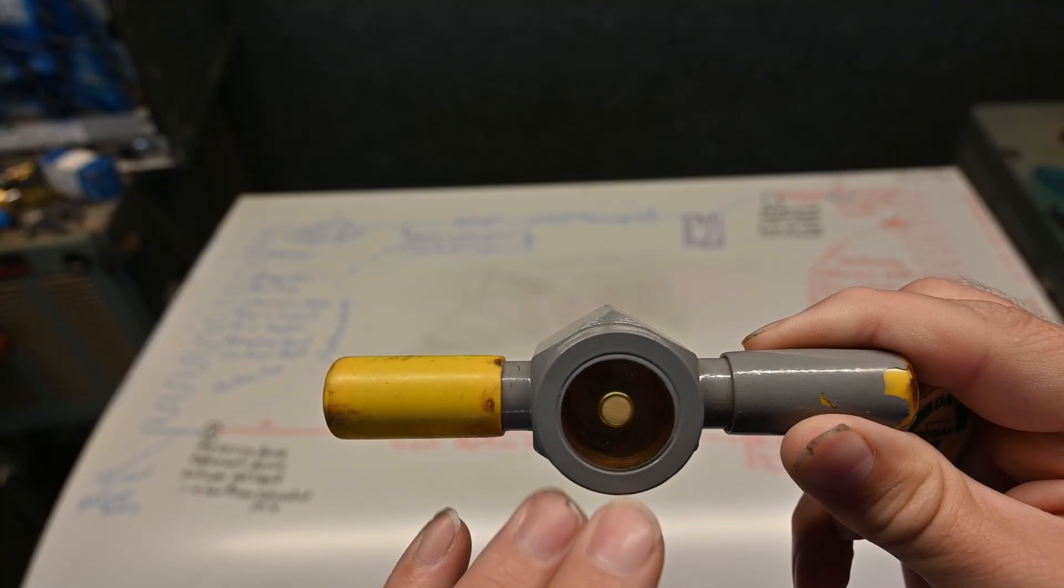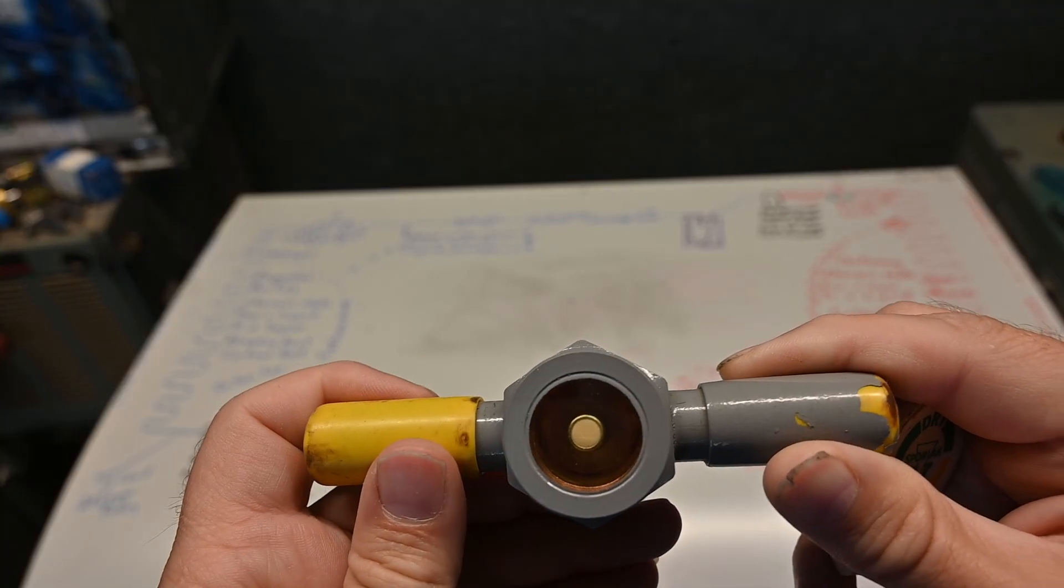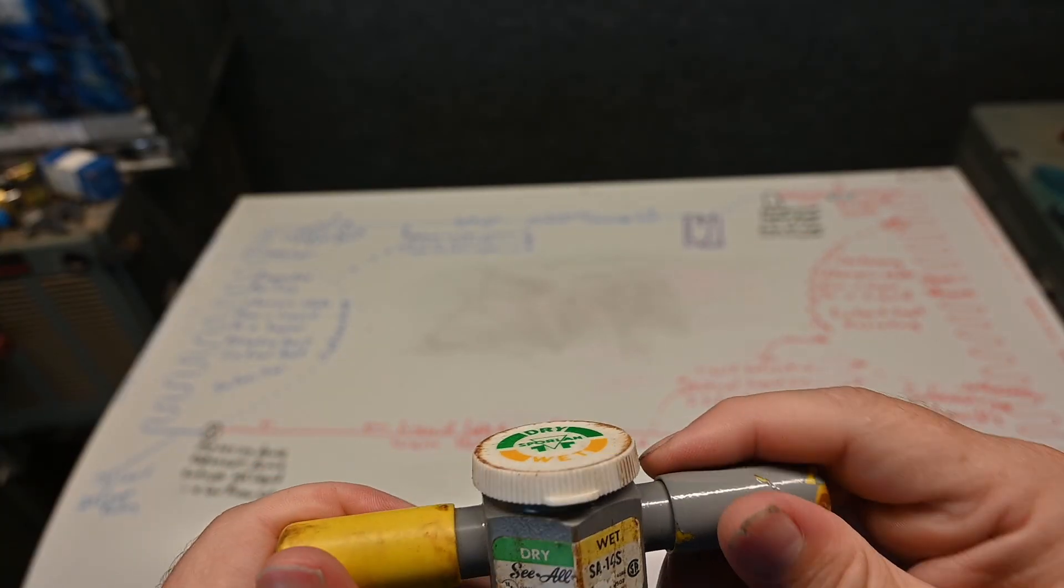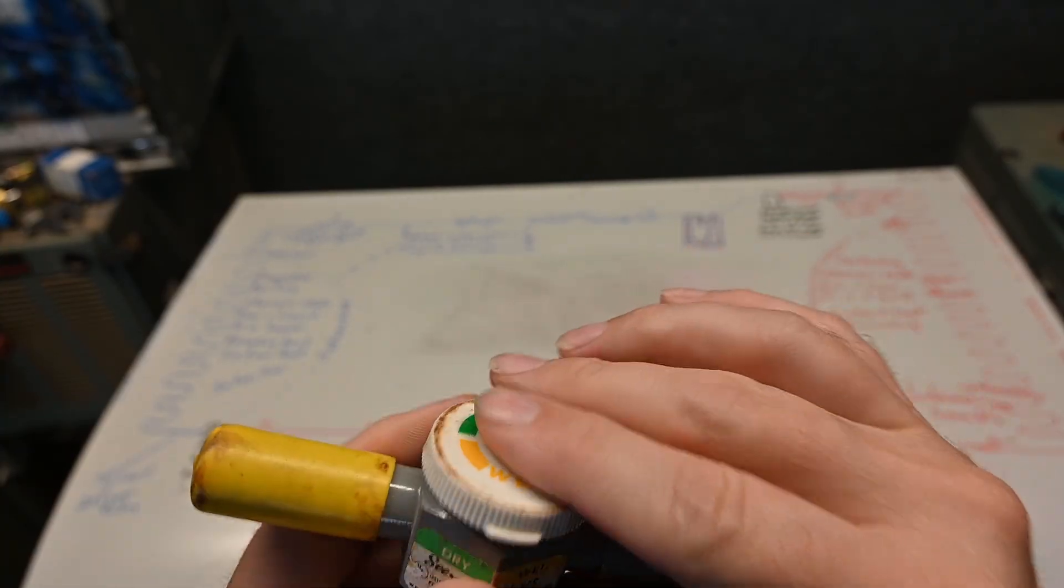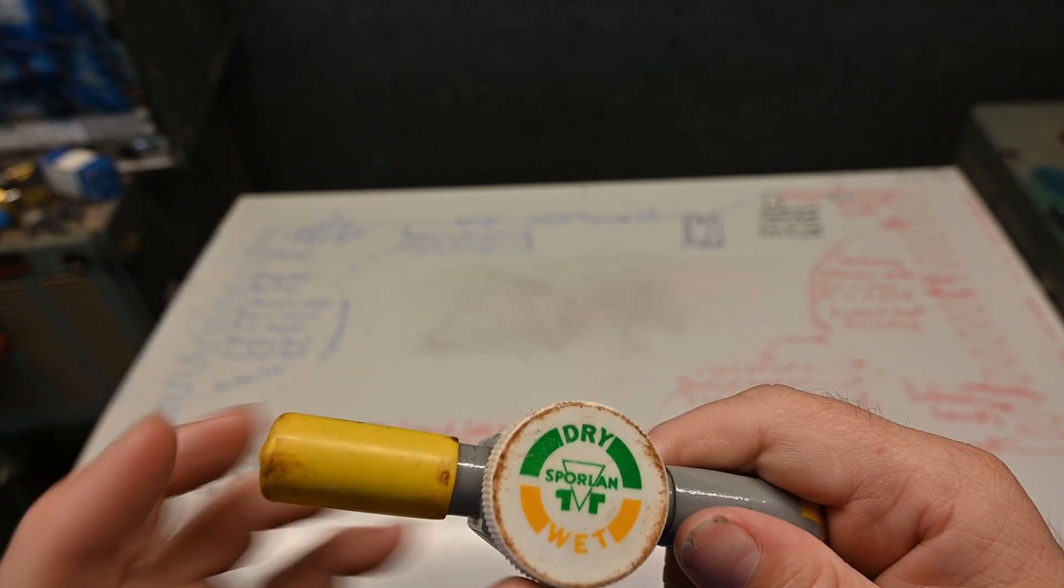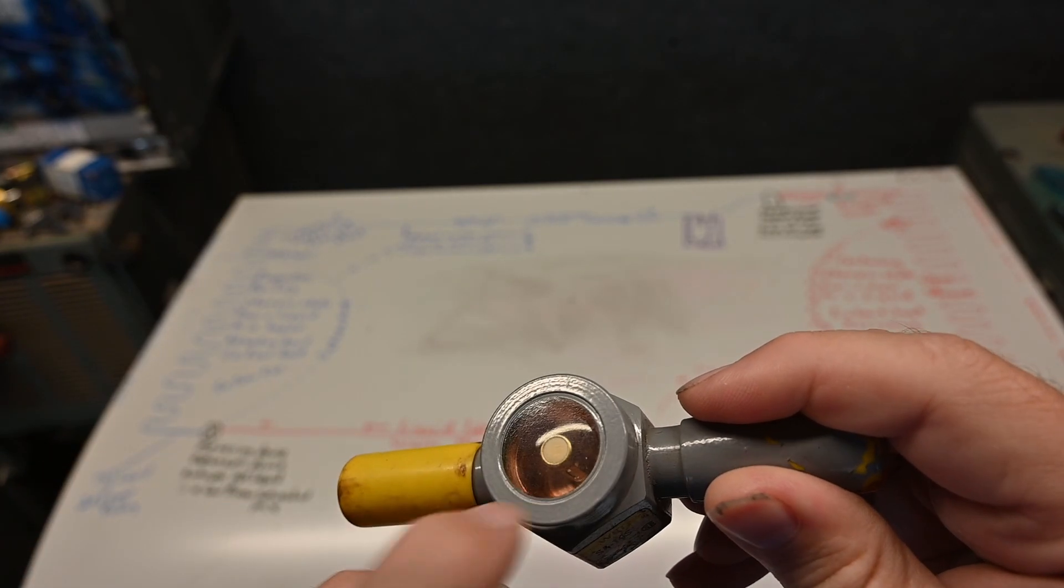This sight glass when you're brazing in has to be protected with wet rags or heat absorbing paste, because as soon as you get this too hot it will break this glass or the glass seal there. It's pretty thick glass but still it can be damaged by heat.